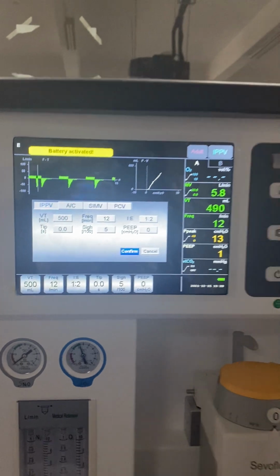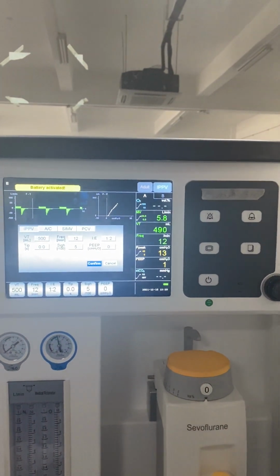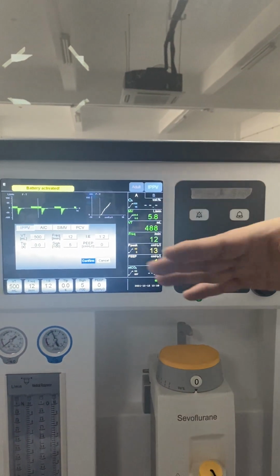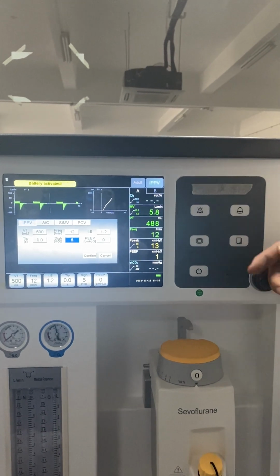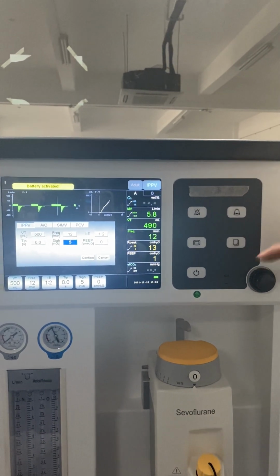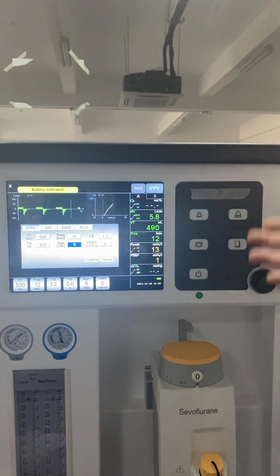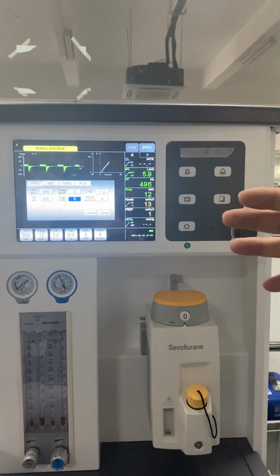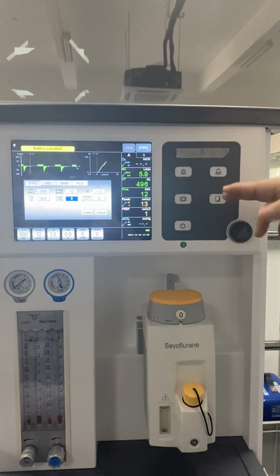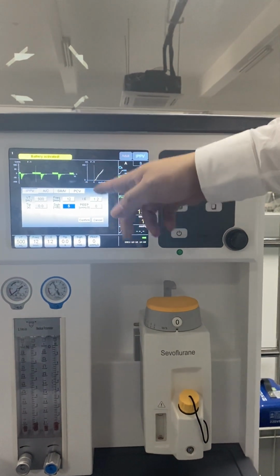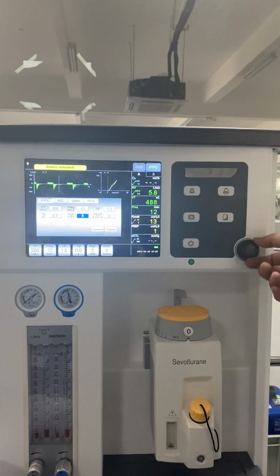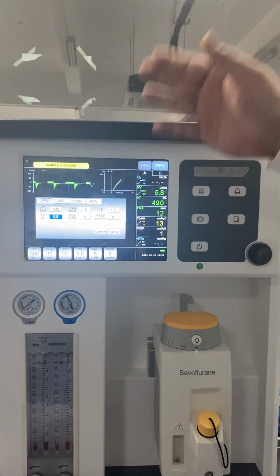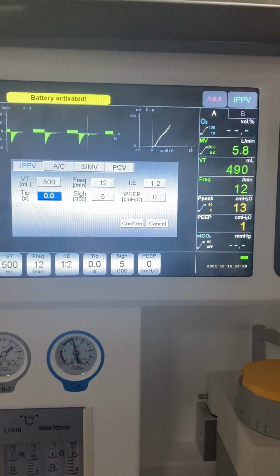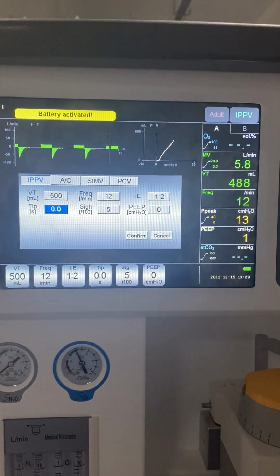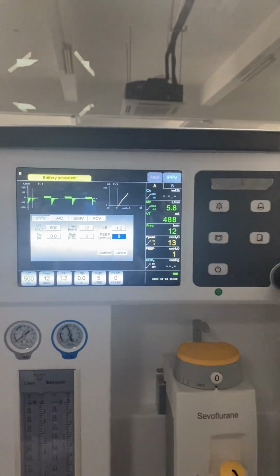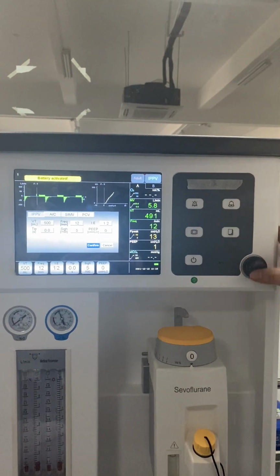So why do we have it here again? Because, for example, if we are doing the operation, and during the operation we want to increase or decrease the parameters, we can only press this button to do it. Because if you go to the standby interface and set it again, it means the ventilation will be stopped, so the patient will be in danger. But if you press here to set the parameter, the ventilation will go on, and after you increase or decrease or even change the ventilation mode, it will immediately change to what you have set. So it will not influence the patient's breathing, and it will keep the patient safe.